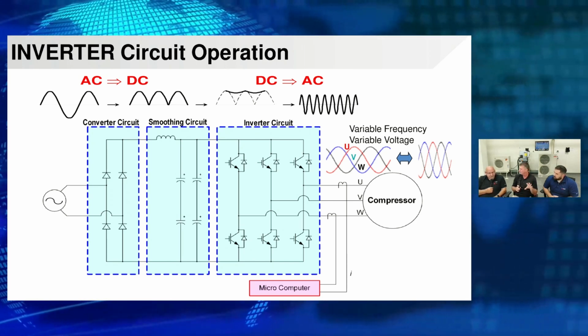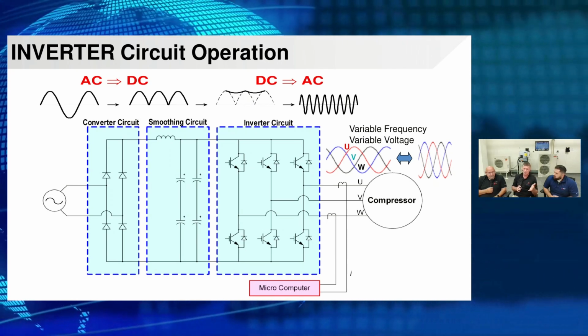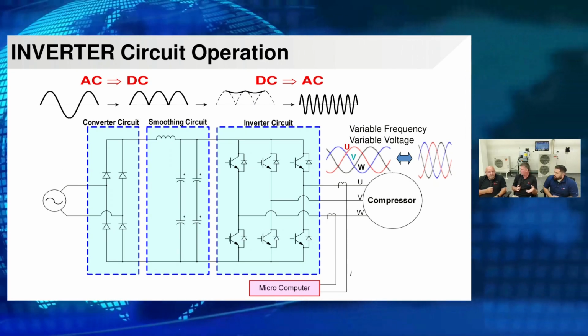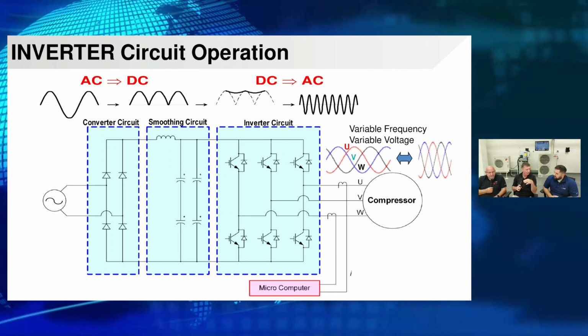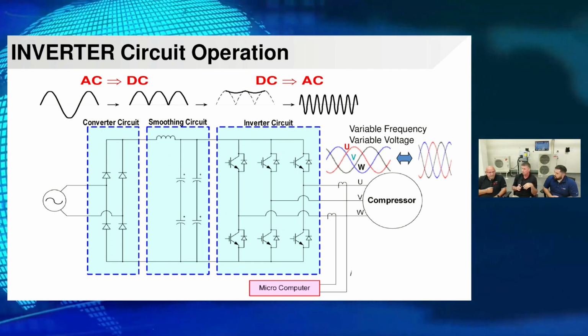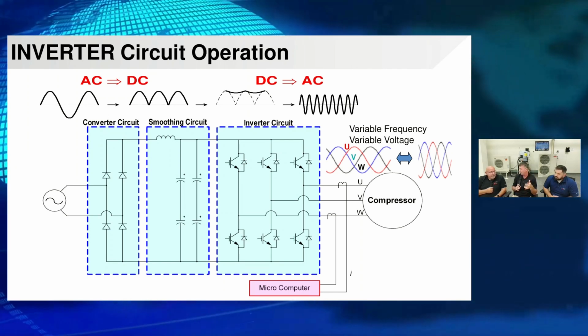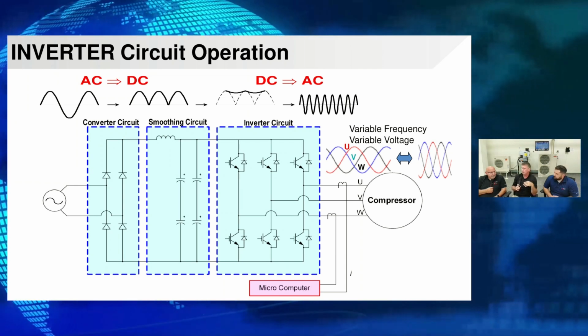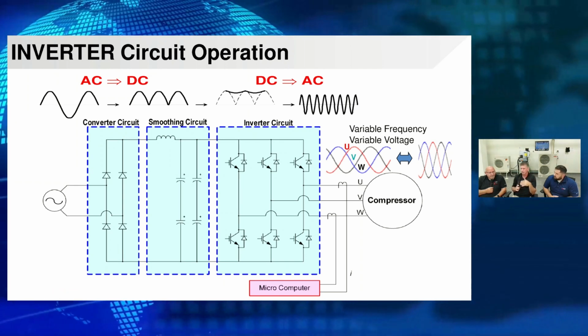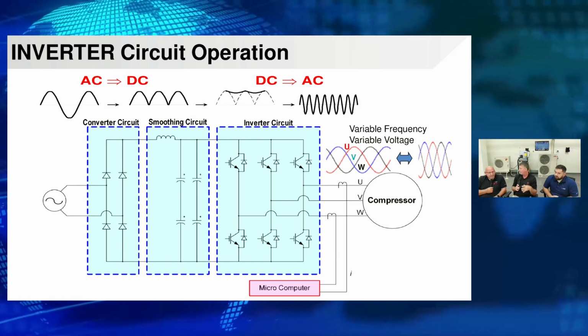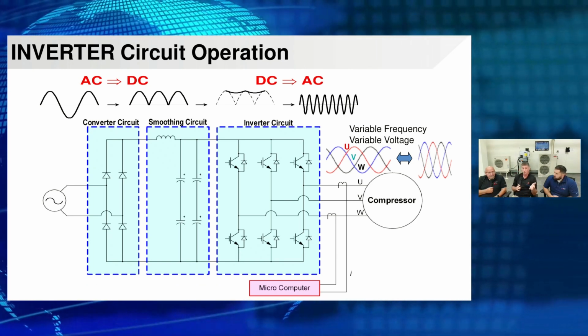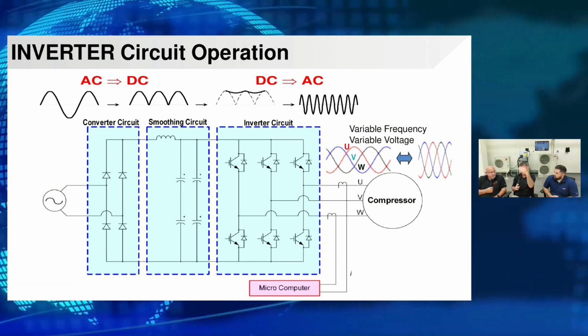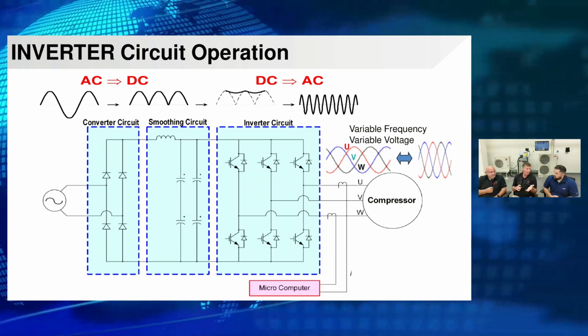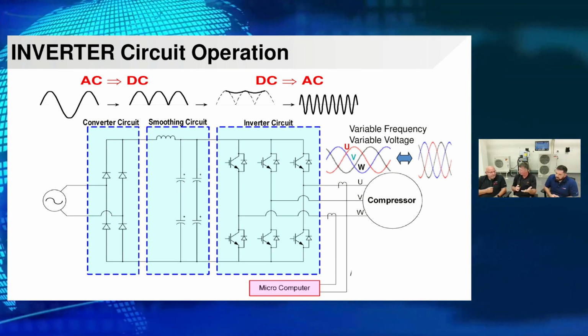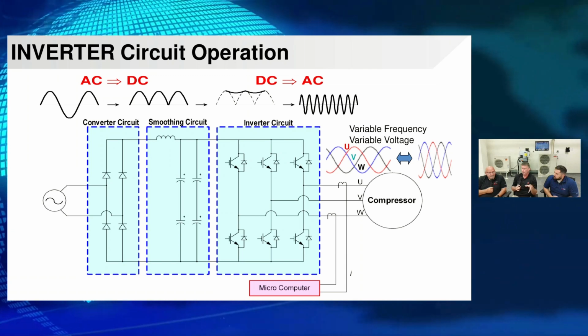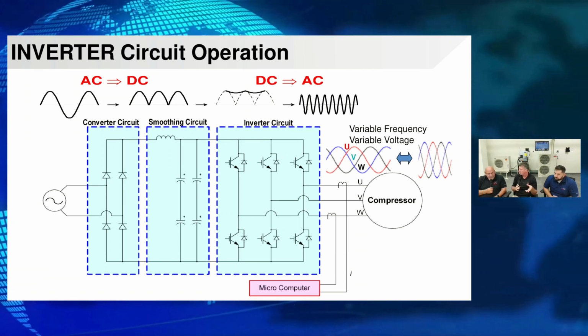And that's usually what I would tell people, because I get a lot of people asking about that 300 volt range. When we start thinking about it, most of our meters are true RMS, root mean square meters, and we're reading an average voltage, not realizing that those peak voltages on a 240 might actually get up there into the 300. That's right. So we're utilizing those peak voltages, building that into a DC voltage, storing it into a capacitor. And so we actually do see that, because even if it was a 120 volt system, we won't see 300 volts. We'll see approximately 130% of that incoming 120. Right. So most of the time we're going to be working on a 240 volt system, and we will see about 300 volts DC.